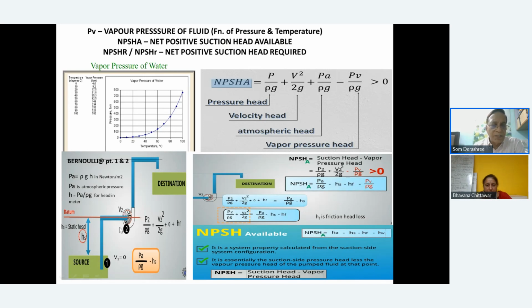Here velocity is 0, here velocity will be some velocity v2, and there is a static head here, HS, which is the static lift, and then there will be some suction losses, HF, in the fluid, depending on the pipe, etc. We'll come to that also subsequently in the slides. And then there's a bend also which will also incur some losses.